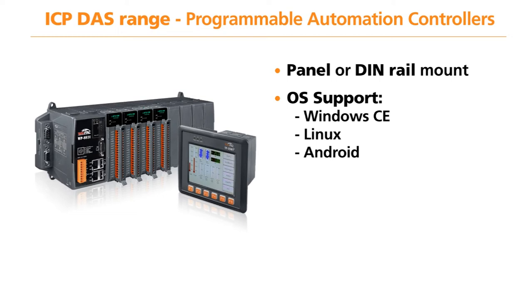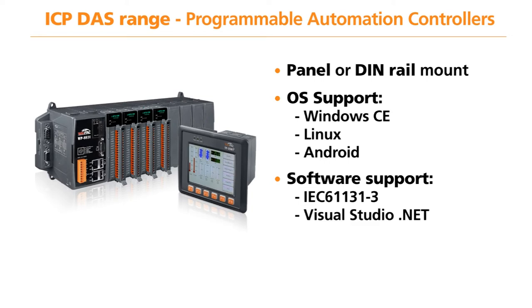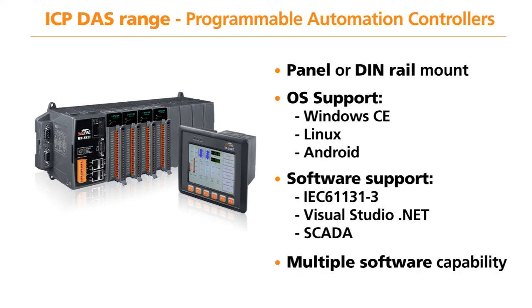To program the Programmable Automation Controllers, engineers can either use traditional IEC 61131-3 program languages, Visual Studio .NET, or most SCADA packages. There is also the option to combine more than one software package into one Program Automation Controller. For example, you can use ladder logic to perform the control functionality and a SCADA program for the HMI interface.